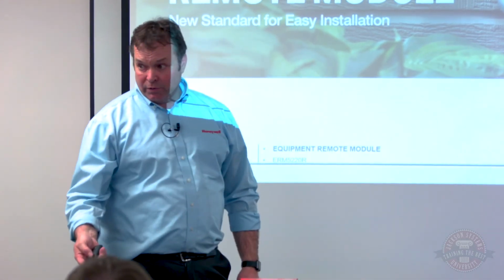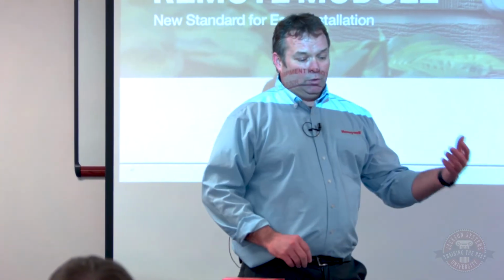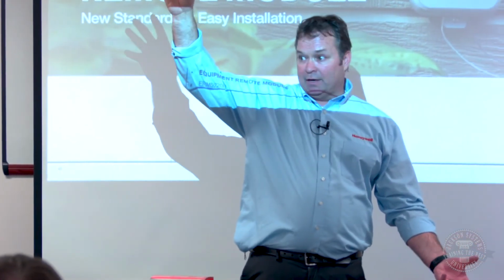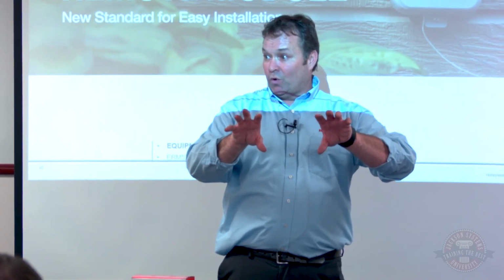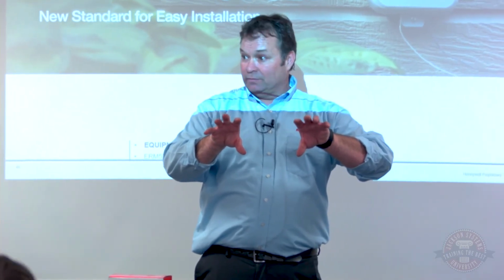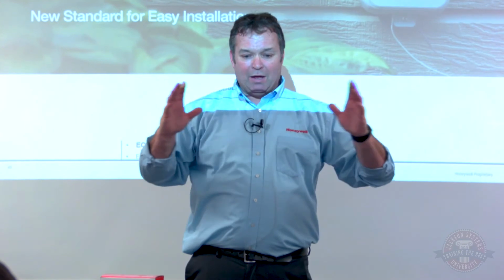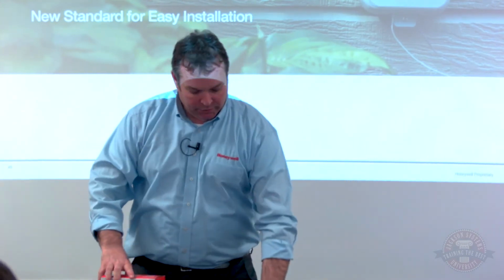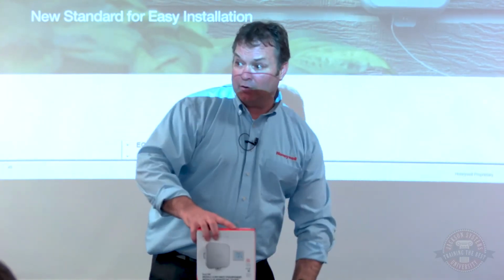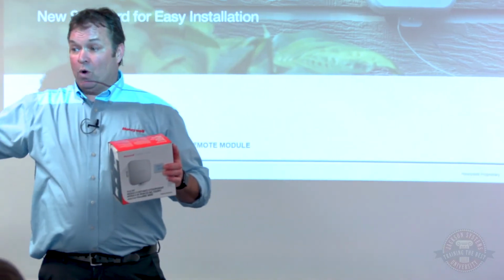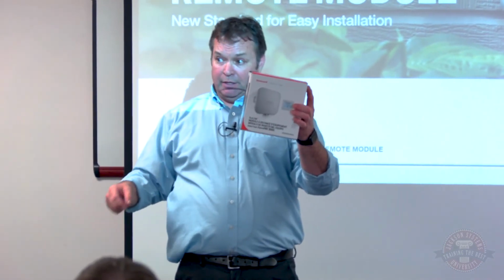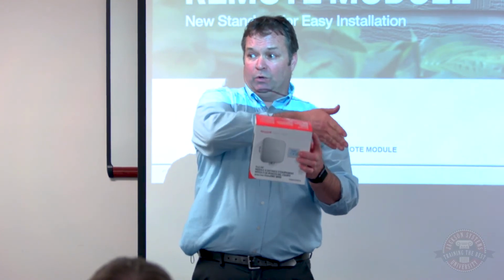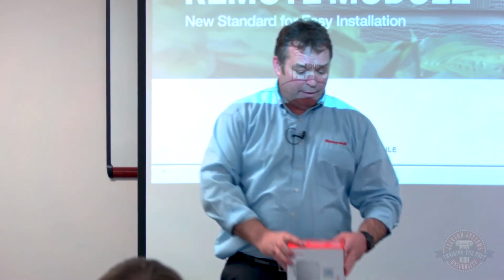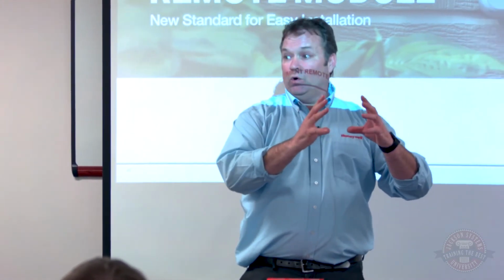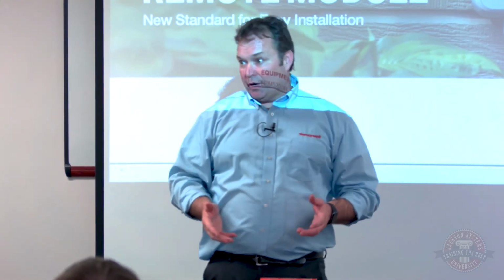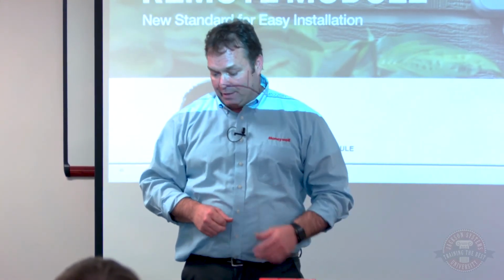If you do boilers, let's say I got a boiler in the basement, an air handler in the attic, and I got 2 T87s on the wall. And you want to say, well, I just want one thermostat. Well, I can put this up at the air handler, this down at the boiler, one out there at the wireless outdoor, because I can use 2 of these. If I take the jumper out, I can hook one to a boiler, one to my condenser, and have that thermostat connected to the internet and upgrade that homeowner with something really, really nice.